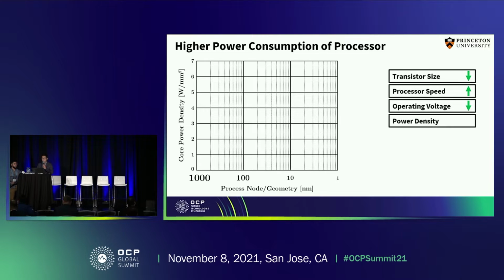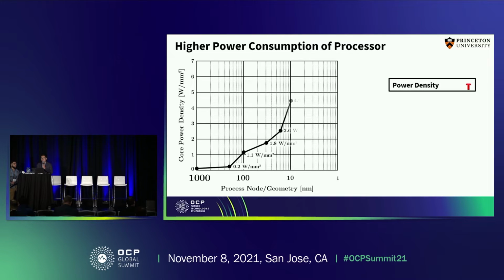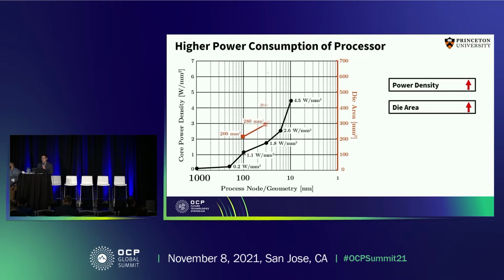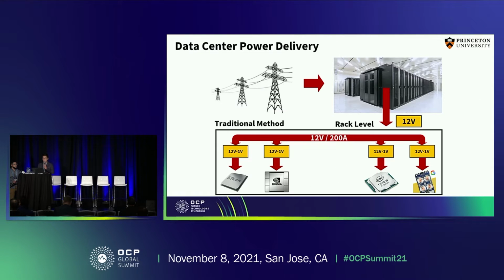Throughout the development of computing, chip manufacturers have been able to keep shrinking the size of the transistor while increasing their speeds and decreasing their operating voltage. The power density of the microprocessor is growing rapidly, from over 0.2 watt per millimeter squared to over 4.5 watt per millimeter squared. At the same time, the overall die area continues to get larger and larger, so we are talking about over 1 kilowatt per processor. We are putting many of these processors in a given server, which creates a lot of challenges in designing the power electronics for these applications.